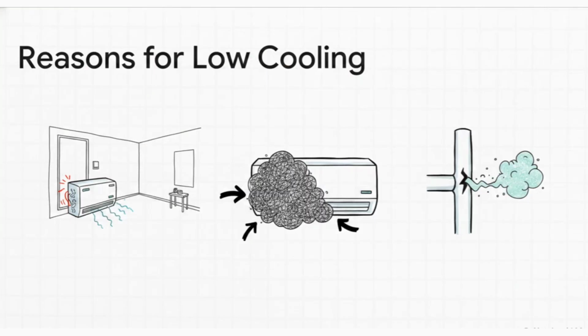Now, what's actually really interesting here is that sometimes there's nothing broken at all. The AC capacity might just be way too small for the room size. The compressor ends up running at 100% capacity, constantly overworking, which, by the way, totally spikes your electricity bills, but it simply lacks the muscle to cool the space. Other times, your air filters are so heavily choked with dust that the cold air literally cannot push through into the room. And then, there's the dreaded refrigerant gas leakage.